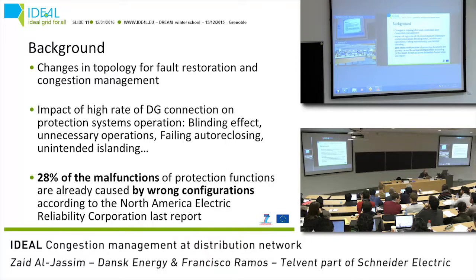The background is the continuous change in topology for fault restoration and congestion management. This is the picture today. There is a high impact of distributed generation connection on the protection system operation. This creates a blinding effect, unnecessary operation, failing auto-reclosing, unintended islanding, etc., and a high rate of malfunction by wrong configuration of the protection devices.